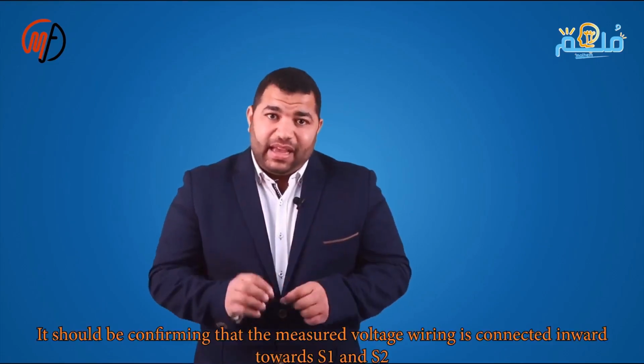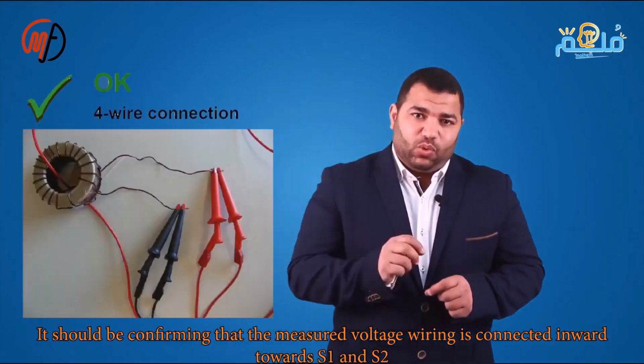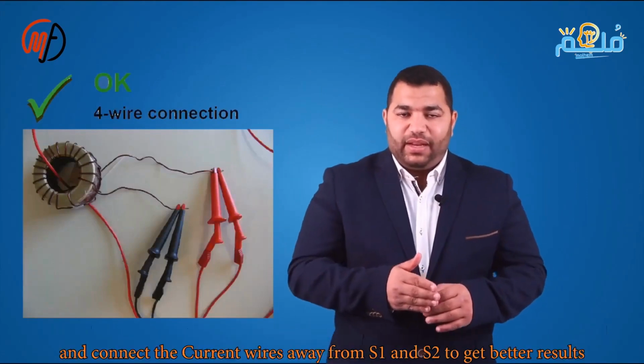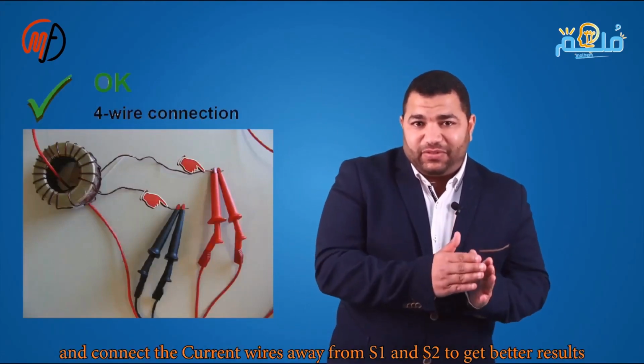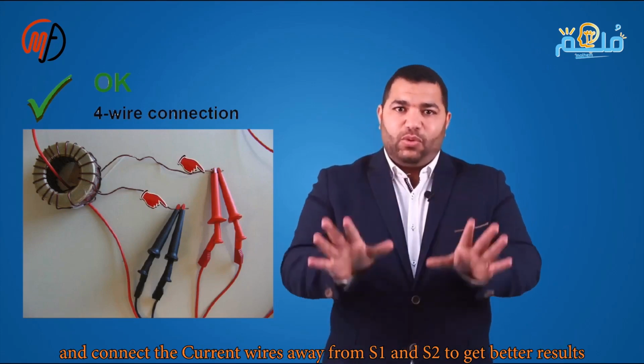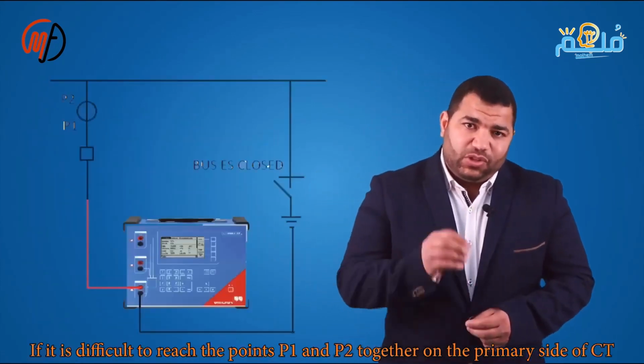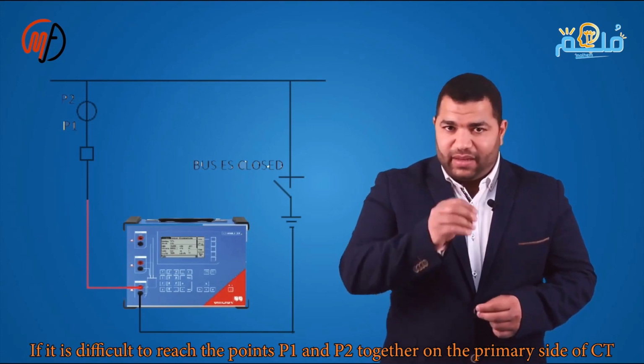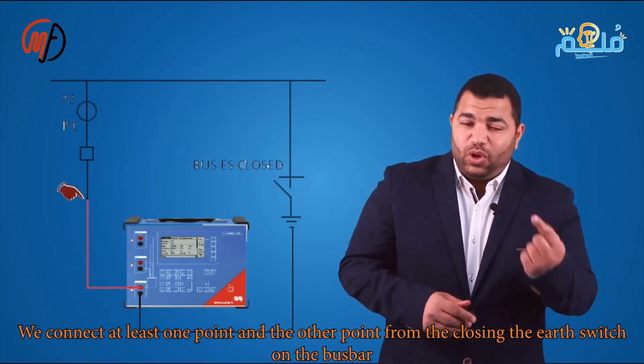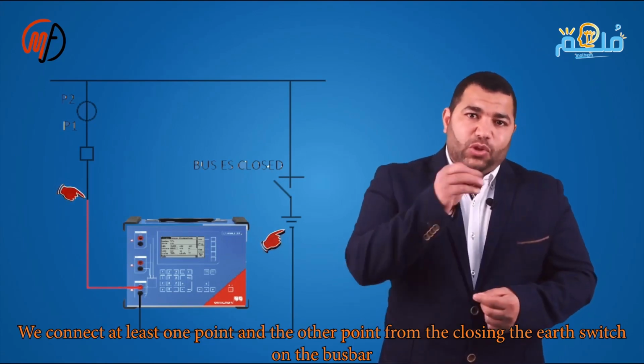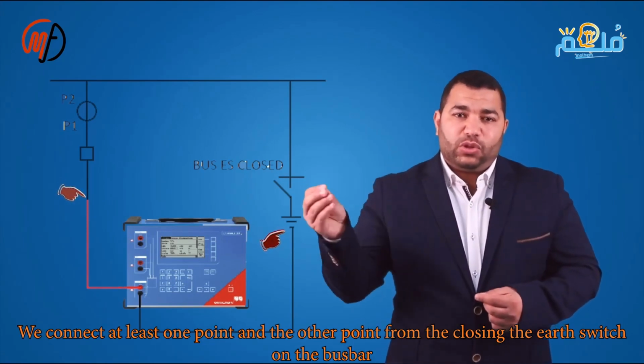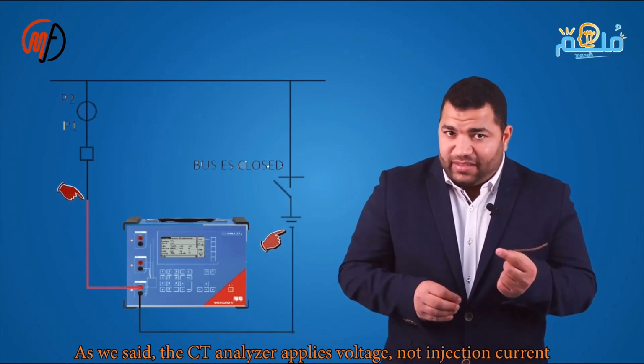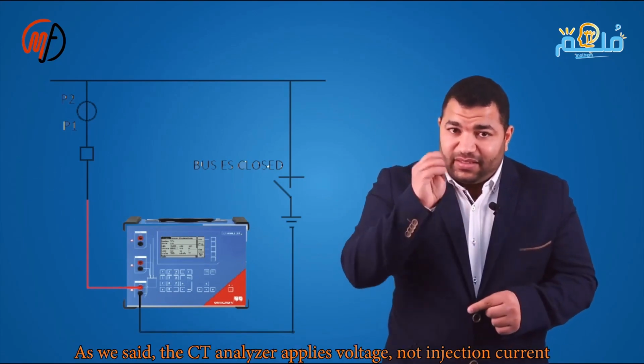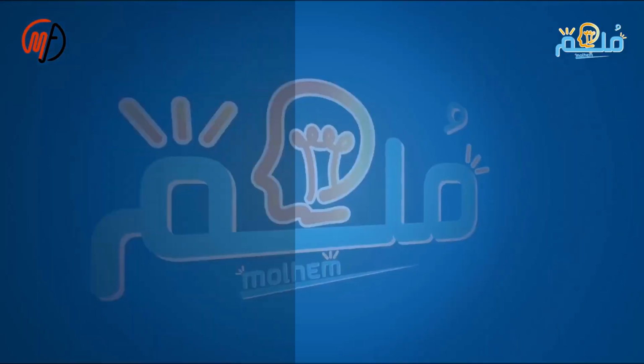Connect voltage wires inward to S1 and S2 and current wires outward. If accessing P1 and P2 on the CT's primary side is difficult, connect one point and close the earth switch for the other. The CT analyzer uses voltage, not current. When testing one tab on a CT with multiple cores, work only on the core being tested. If issues arise during bushing CT tests, short circuit uninspected cores and ground other phases. You can also test the VT using the CT analyzer with these connections.